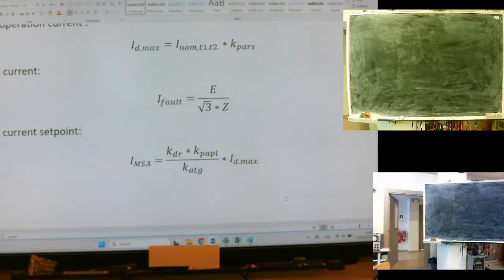Terminals without a voltage section are much cheaper. At the moment you need this negative sequence protection logic, you need voltage circuits. With a terminal without voltage, all this voltage section is cheaper. So you need a more expensive terminal, how can you get it? We don't have any money. Blah, blah, blah. Push them hard. Push them. Because it's a small investment, but it can save huge money. So you also need to be aggressive on funding.